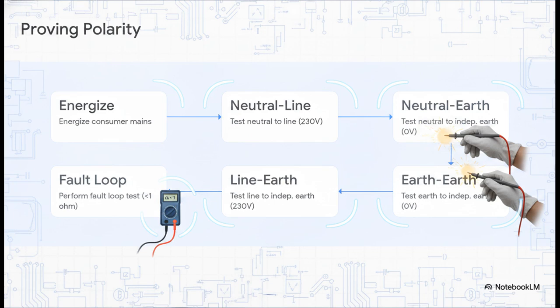Once the consumer mains are carefully energized, you verify the voltages against your independent earth. The main neutral to the line terminal should read your phase voltage, 230 volts. The main neutral to your independent earth, that must be 0 volts, proving the neutral is not energized. The earth to independent earth must also be 0 volts, but the line terminal to independent earth must read 230 volts. Finally, you run a fault loop impedance test on the active and neutral, which needs to give you a result of less than 1 ohm. Hitting these exact numbers is how you prove polarity and neutral integrity without a shadow of a doubt.